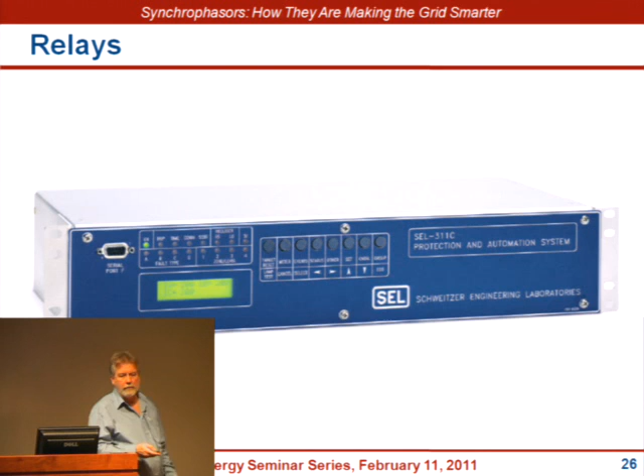So what's adaptive protection? Well, adaptive protection is where, in normal times, your relaying is set for all lines in service, normal conditions, everything fine, everything healthy, and you set it for certain conditions, certain levels of fault current, certain levels of voltage, under frequency, and so forth. When things go wrong, lines go out, generators go out, loads go on and off the system, you're basically hoping that that relay is still seeing more or less the things it should be seeing and will operate more or less the way it should operate.